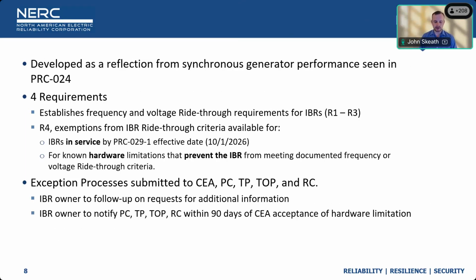So this was developed as the IBR counterpart to synchronous generator performance from PRC-024. PRC-024 is largely a relay setting standard for frequency and voltage protective devices for synchronous facilities. This is a defined ride-through, which is a little bit dissimilar from PRC-024, as PRC-024 focuses on settings in the protective equipment, whereas PRC-029 looks at the performance as seen at a certain point in the plant for exchange of current and ride-through type behavior. But it essentially looks at frequency and voltage, and they're very similar in that the goal is to ensure certain performance from those types of resources. So it used PRC-024 as its starting point and reflection for synchronous resources, and then altered it to meet the expectations and directives of 901.